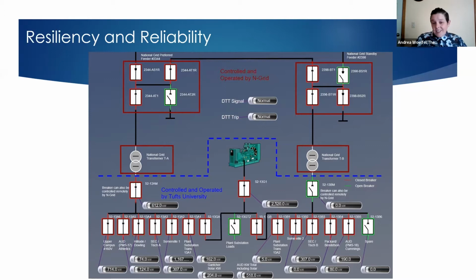We have redundant electric service. I don't know if it's hard to see from the drawing, it's very familiar to me, but we've got 2 utility feeders coming from National Grid local at 24,000 volts. That's knocked down to work in parallel with us with redundant feeders. So if there's any kind of problem on the grid, we can swap or split the load. There's all kinds of options here, and it can all happen on an automated basis.